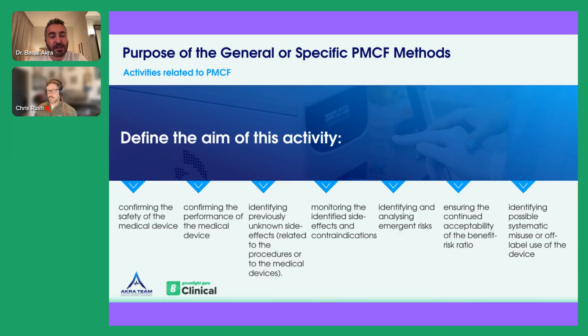Not every device would be required to do a post-market clinical follow-up study or a post-market clinical follow-up registry. Some devices might be able to rely on general methodologies which are defined in the legislation. This is why the legislator said we need to have a post-market surveillance plan for every device, and within that plan, a post-market clinical follow-up plan.